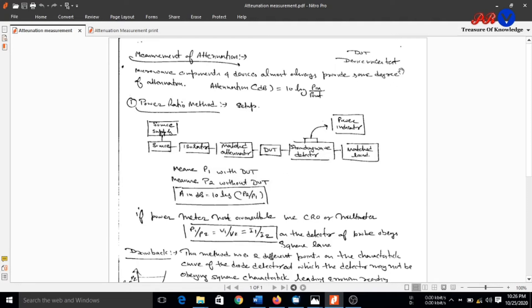DUT stands for device under test. In this way, we can measure attenuation using the power ratio method. If a power meter is not available, we can use a CRO or multimeter. The detector obeys the square law, meaning P1/P2 = V1/V2 = I1/I2, because the output from the detector is proportional to voltage or current, and the square of voltage is proportional to power.